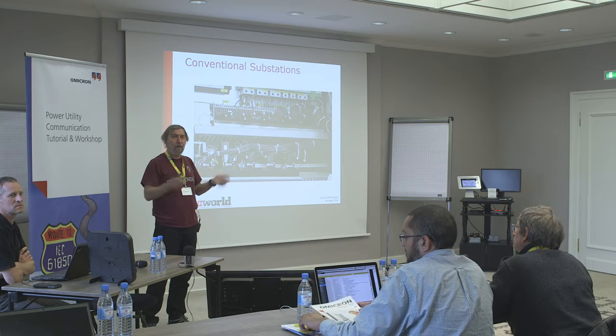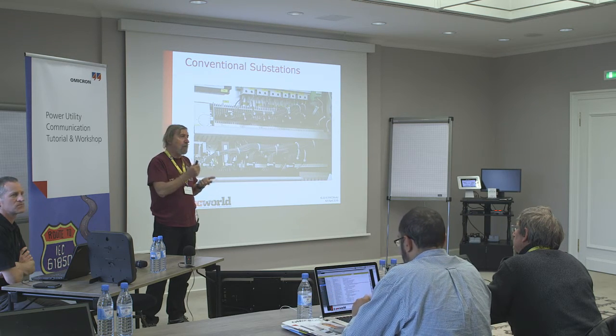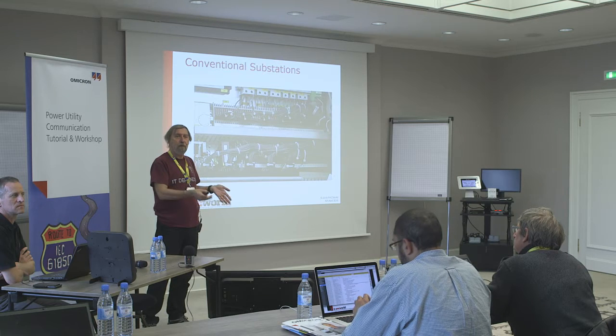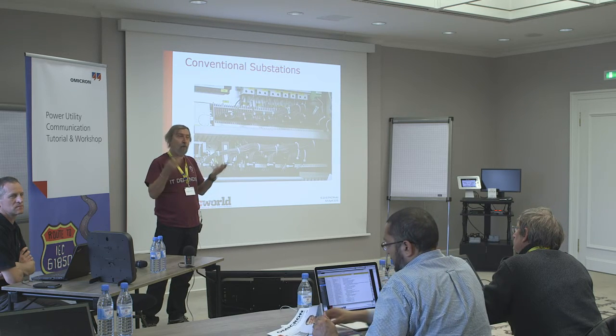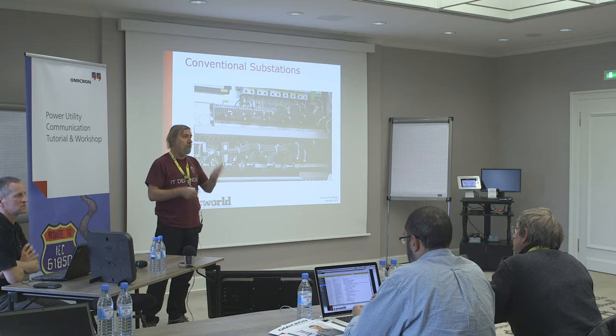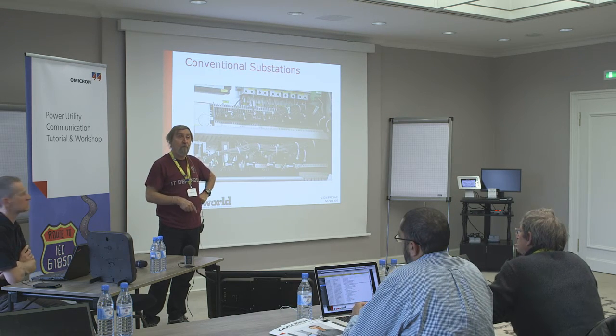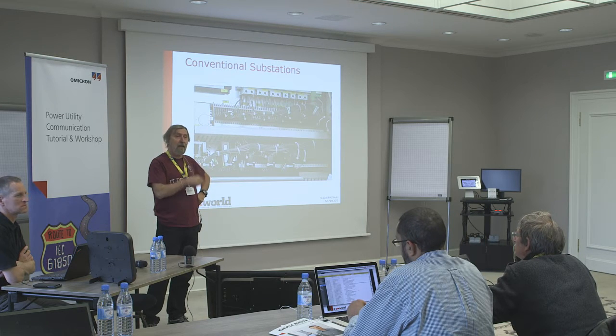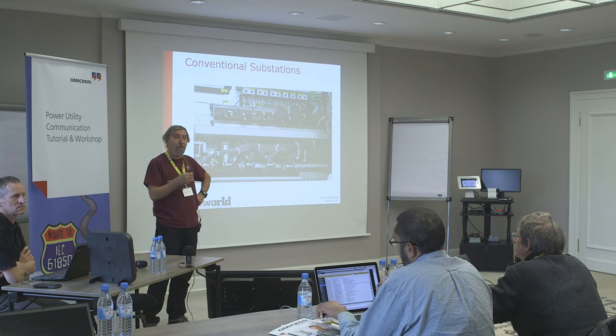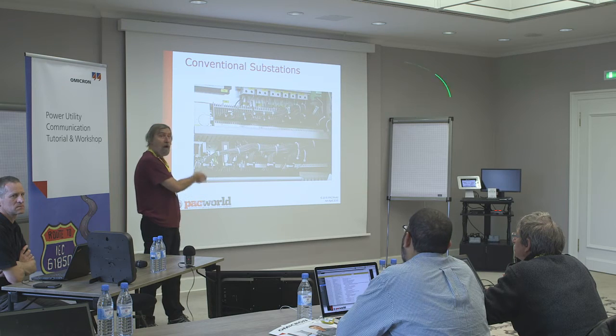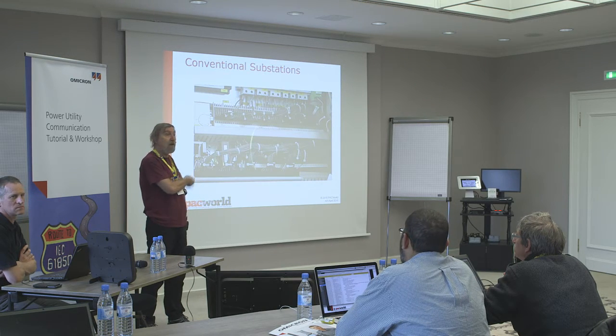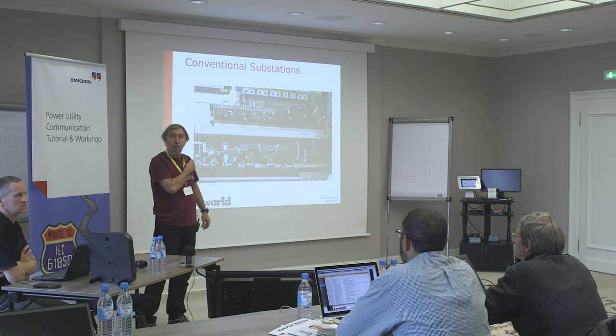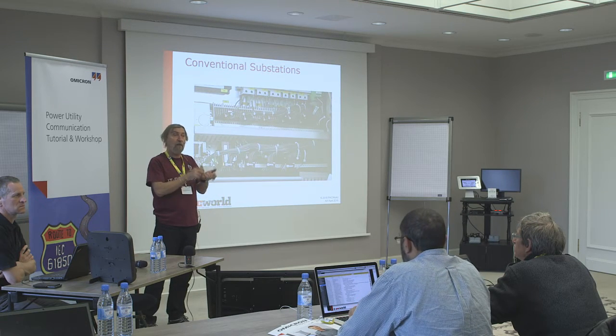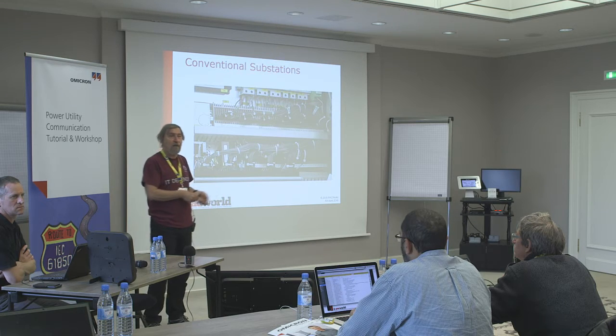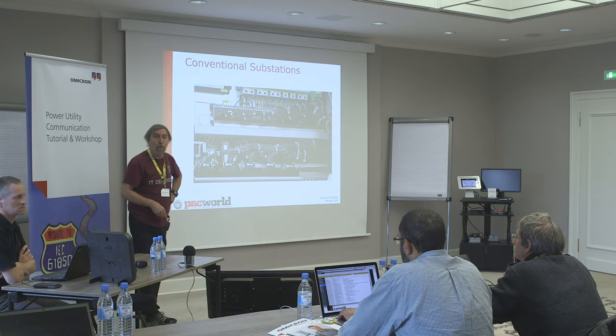And when I asked him why, he said, because they couldn't find... You heard about the fracking, okay? The fracking when they inject pressurized water into the ground to extract the gas so they can, you know, use it for vehicles or power stations or whatever. In order to be able to build the substations for the fracking, they needed very quickly to have substations. And they couldn't find enough technicians to do all this wiring using hard wires. So they said, we are going to replace all of this with GOOSE, and this is what they did. And they had a lot of savings, not only in the cost of the substation, but in the time that it took to put it in service.